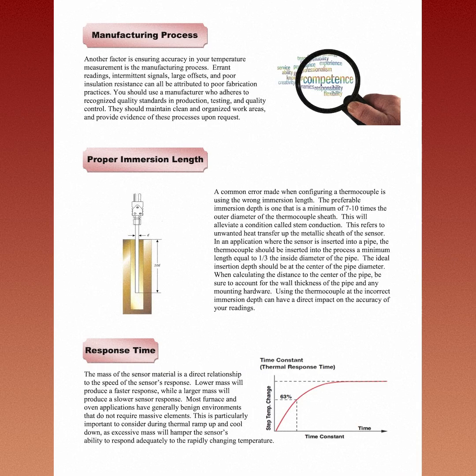Proper immersion length. A common error made when configuring a thermocouple is using the wrong immersion length. The preferable immersion depth is a minimum of 7 to 10 times the outer diameter of the thermocouple sheath. This will alleviate a condition called stem conduction. This refers to unwanted heat transfer up the metallic sheath of the sensor. In an application where the sensor is inserted into a pipe, the thermocouple should be inserted into the process a minimum length equal to 1/3 the inside diameter of the pipe. The ideal insertion depth should be at the center of the pipe diameter. When calculating the distance to the center of the pipe, be sure to account for the wall thickness of the pipe and any mounting hardware. Using the thermocouple at the incorrect immersion depth can have a direct impact on the accuracy of your readings.